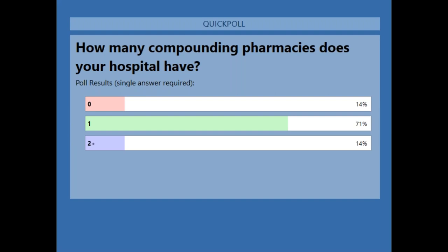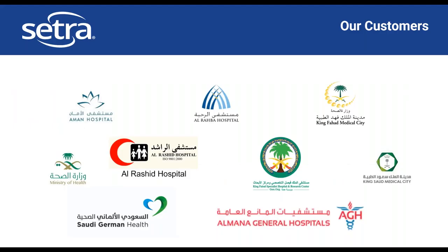A question from Wasim: can the Setra Light be calibrated on site? The Setra Light does have a zero calibration capability on site, so you can set the zero. However, there is not currently a version of the Setra Light that supports use of a pressure calibrator for full verification and validation. The zero calibration typically covers most people's requirements for an extended period.